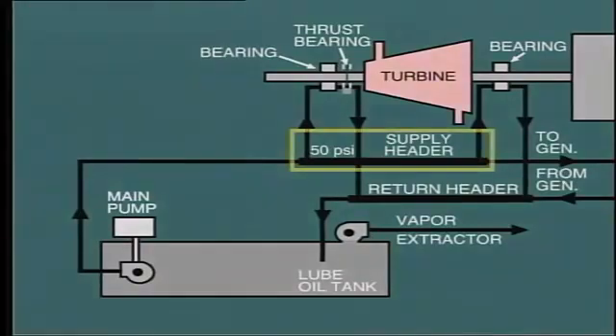Maintaining the cleanliness and purity of the oil is extremely important to good turbine operation. The lube oil is sampled at regular intervals, say monthly or bimonthly, and analyzed for impurities and other characteristics. The supply of lube oil is so vital that a standby pump must always be provided and maintained, ready for startup on automatic control. In case of a loss of all auxiliary AC power—for example, a turbine generator trip in a facility with no station service backup—many machines are equipped with a DC oil pump fed from the station battery to prevent damage to all of the bearings.